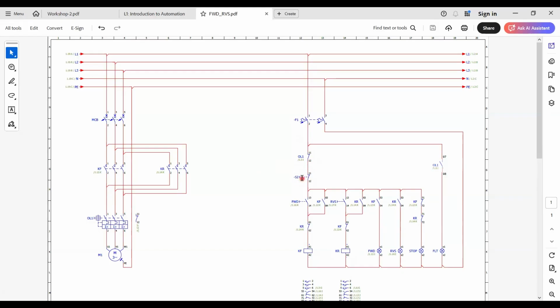This is the stop push button. Normally it is not pressed until you want to stop the motor, then current comes to here. So assume that we want to start the motor in the forward direction. We need a forward motor starter push button. This is the starting momentary push button for the forward direction. When you press it, this path is now completed and current goes through here. This is the KR, that is the reverse contactor, normally closed contact, which means this has to be closed when this is not energized, which means you will never be allowed to turn on the forward contactor in the event when the reverse contactor is energized. We call that an interlock. So if the reverse contactor is de-energized, this is closed, and only then are you allowed to pass the current through here and energize the forward contactor.